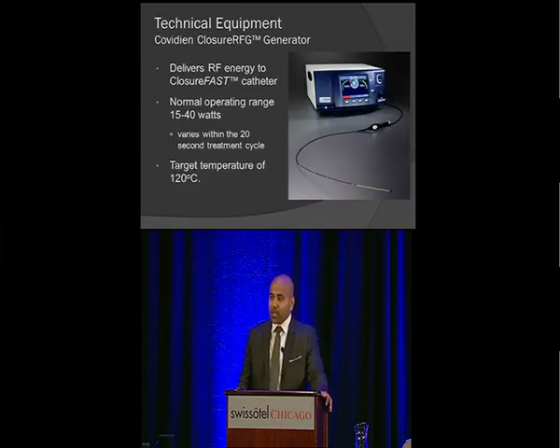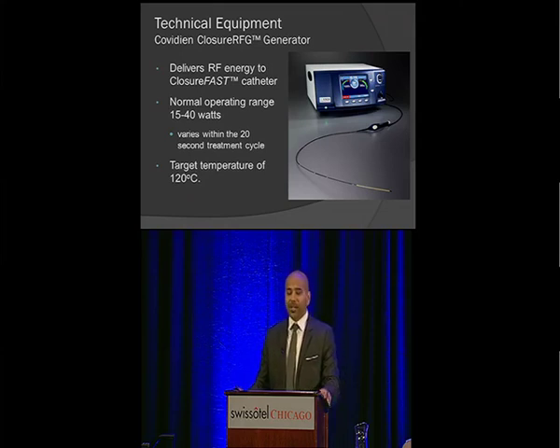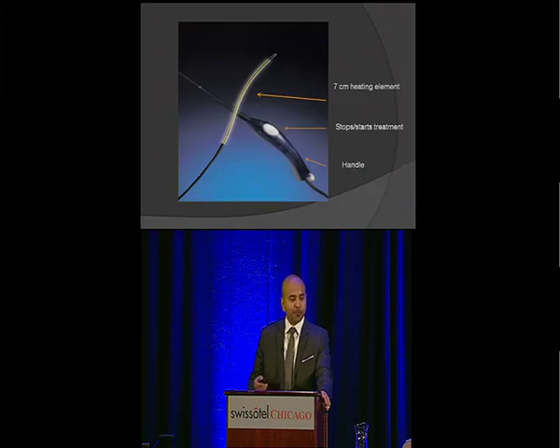So what is the equipment that's required? You require a generator. This is a picture of the Closure generator. It delivers RF energy through the ClosureFast catheter. The normal operating range is about 15 to 40 watts, and you treat for 20-second cycles. And there's any number of segments that you can treat, that I will get through. The target temperature of the tip of the coil is about 120 degrees Celsius, so it gets pretty hot.